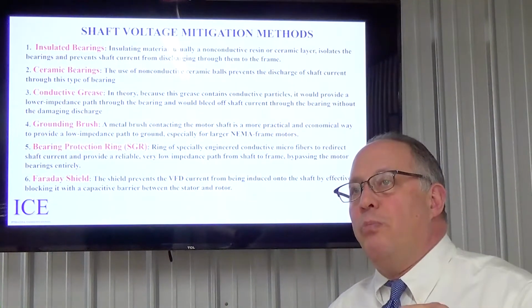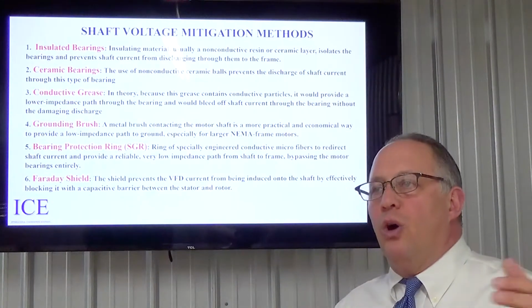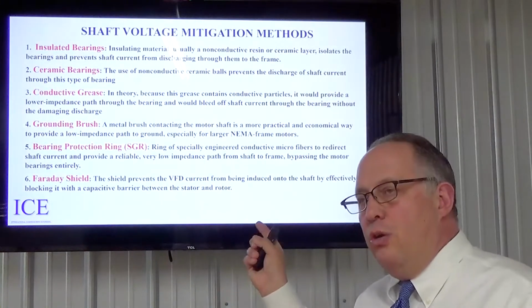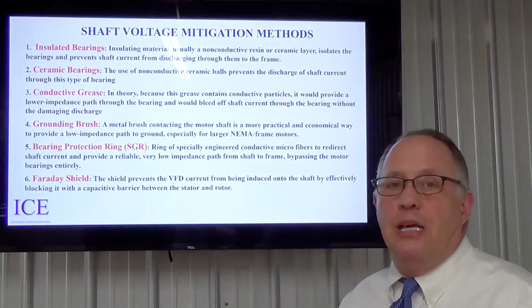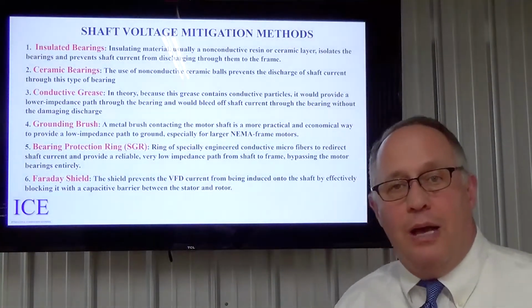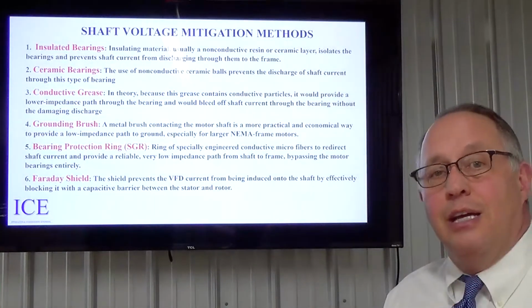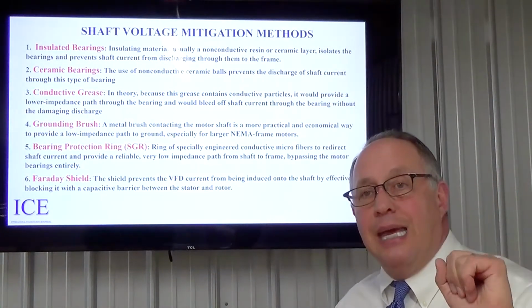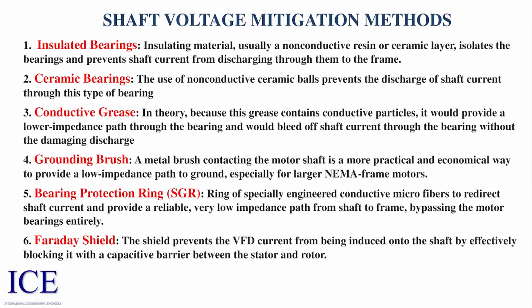That is more prevalent if you go with a larger and larger motor, which you may have. You will see that insulated bearings can be rather expensive to install. It's a good system, but it can get to be expensive. Ceramic bearings. The use of non-conductive ceramic balls prevents the discharge of shaft current through this type of bearing.